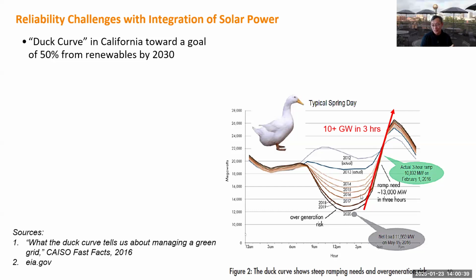You need to have a lot of energy storage, because energy storage can respond much faster than the conventional generator. Or you can have a lot of spinning reserve. By spinning reserve, I mean conventional generators that are running all the time but not generating electricity. So when you need their power, they will just increase their generation immediately, which means you still keep those generators in the grid.